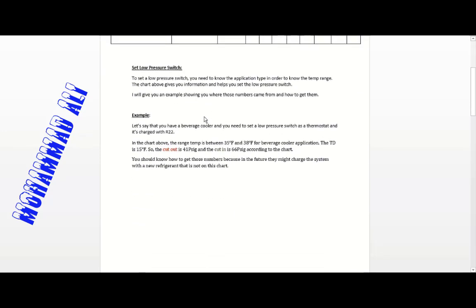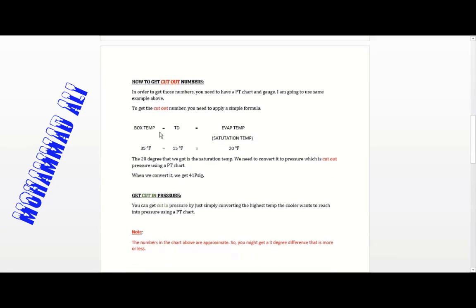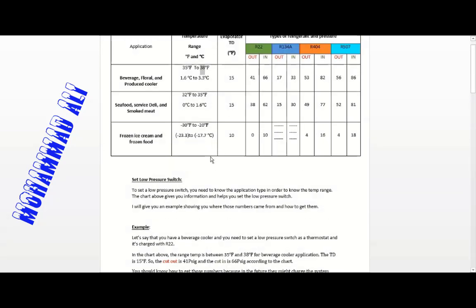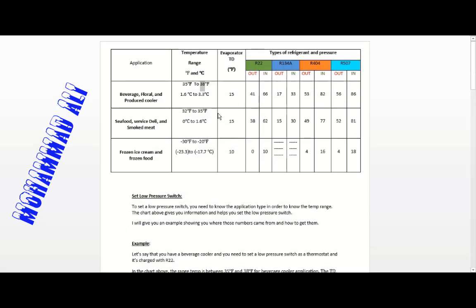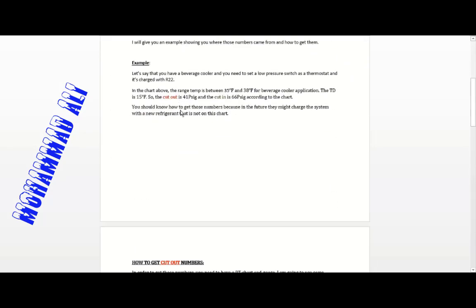We have a simple formula: box temperature minus TD equals evaporator temperature (or saturation temperature). Since we're finding the cut-out — meaning when we want the compressor to stop — the compressor should stop when the temperature reaches 35°F. We don't want to go lower than 35°F, so the box temperature is 35°F.